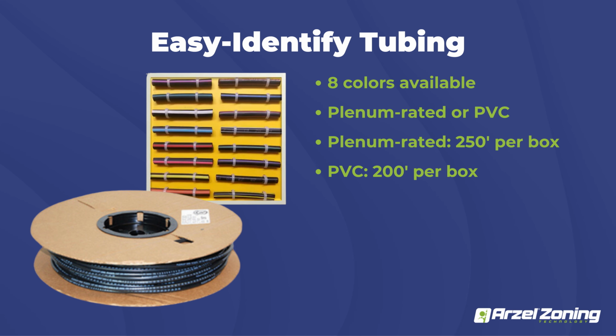It'll work either way. So if you guys are only doing a 2-zone system, you don't want to buy 2 boxes of tubing because it's 200 feet in a roll. You're more than welcome to run them in the same colors. I would just recommend maybe marking the dampers on what zone they are. Just take a marker and mark the damper itself.